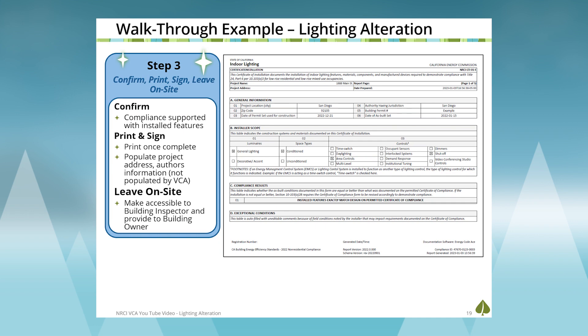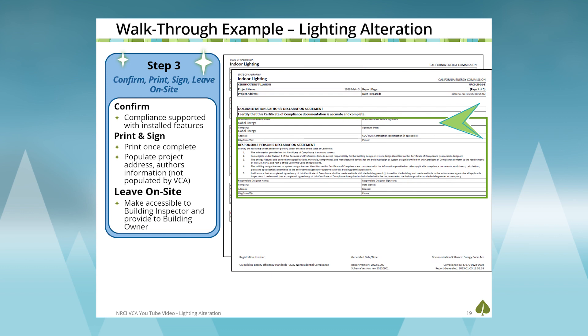Now we're on step three. This step requires putting some additional information into the forms. Due to California's privacy protection rights, the VCA will not collect address or direct contact information. Use a PDF tool to fill out the project address on each page of the compliance form. On the last page, sign as the documentation author, provide address, city, zip code, and phone number, and collect the signature of the responsible person — the liability signature as dictated by the Business and Professions Code Division 3, typically the licensed installing contractor, though the general contractor can sign if the installing contractor is no longer available.